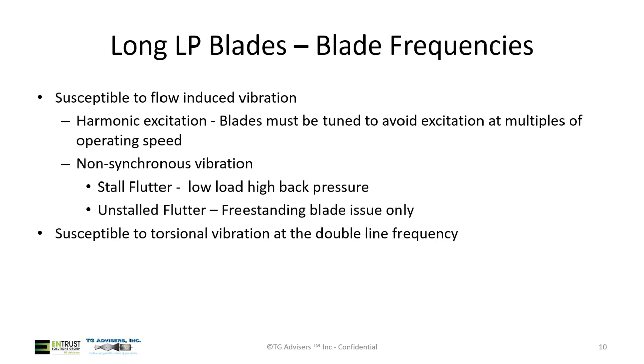And then unstalled flutter, that's a high load, high flow issue, freestanding blades only. So if you're going on a freestanding blade, you want to have some conversations with the OEM around that and the fleet history.